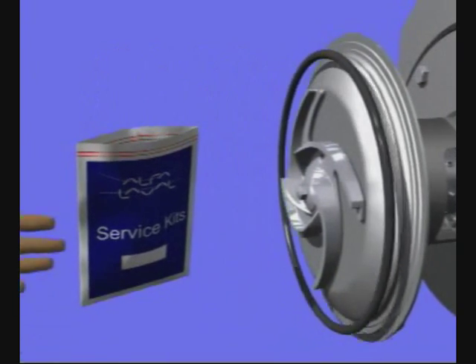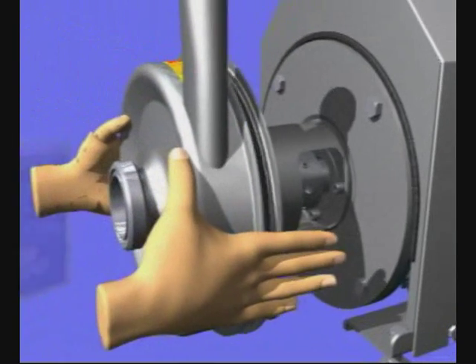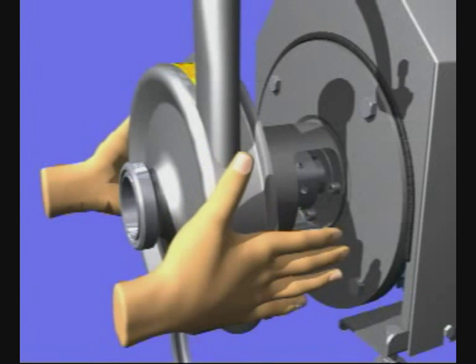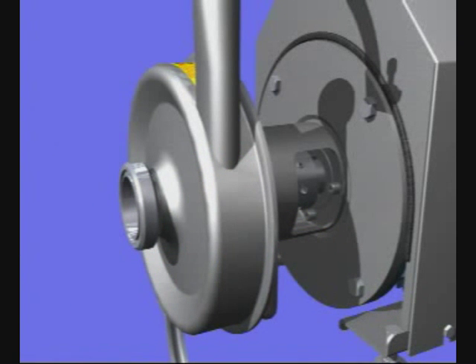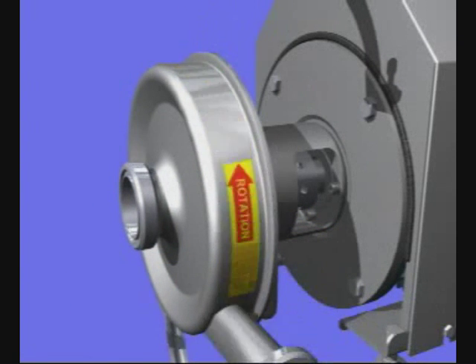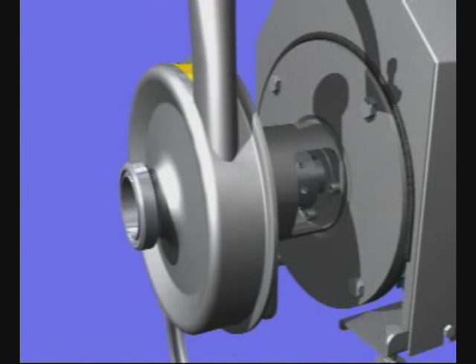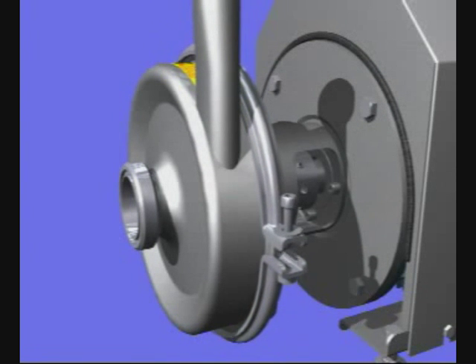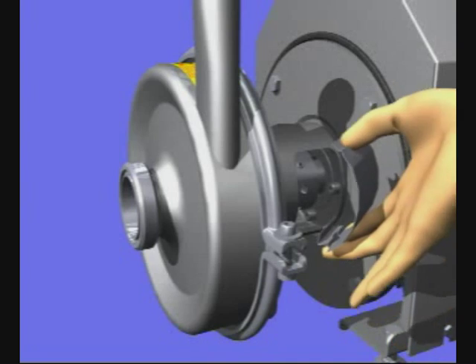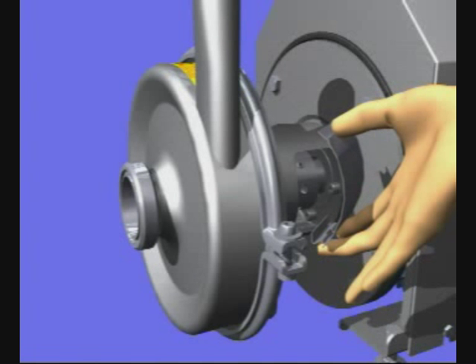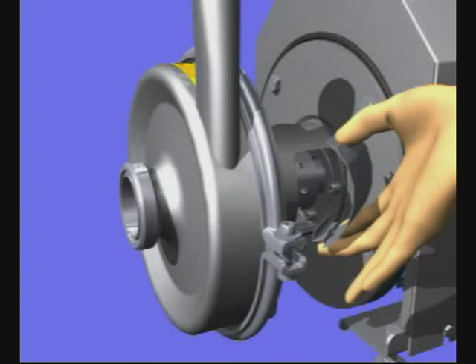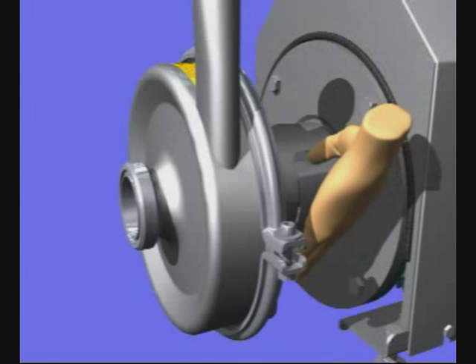When you press the pump casing to metallic contact, it will stay in place, allowing you to work with the clamp using both hands. The outlet can be placed in any direction you wish, enabling you to adjust exactly to your pipework. The safety guard is easily fixed with your hands only. Press the guard slightly and it will lock by itself.